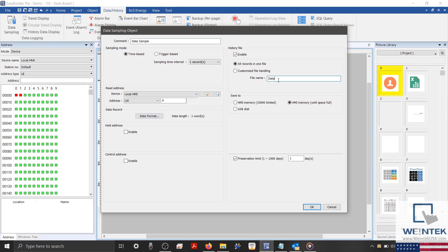During this demonstration, I have chosen to save all records within a single named file that will be stored within our HMI's internal memory. The preservation limit, as shown below, is set to one day, meaning that the history file from the previous day will be saved within the HMI's internal memory, and the file generated on the current day will replace that file on the subsequent day.